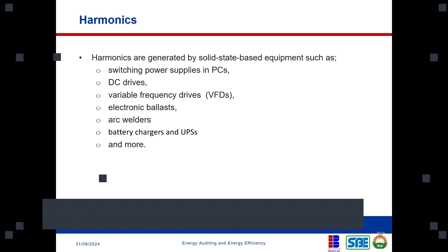So what are the causes of these harmonics? Harmonics are generated by solid-state-based equipment, such as switching power supplies in PCs, DC drives, variable frequency drives. Any system that converts AC current to DC current introduces harmonics. Those are non-linear loads. Harmonics are generally the distortion of a normal electrical current waveform, generally transmitted by a non-linear load. Examples of these non-linear loads are switching power supplies and variable frequency drives, and generally any system that converts AC current to DC current is a non-linear load.